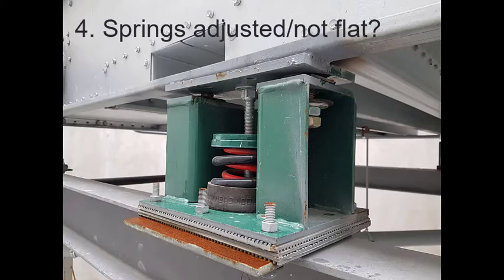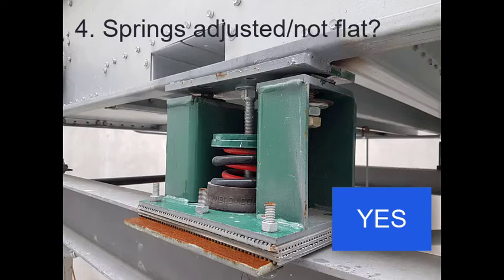Are the springs adjusted? Yes, we saw that all the springs had been compressed. The unloaded free height of these particular springs is 5.5 inches. We can tell these have been adjusted since they are now shorter. In some cases, an acoustical consultant will want to measure this static deflection to check for compliance with a specification. The greater the deflection, the more frequencies will be isolated.